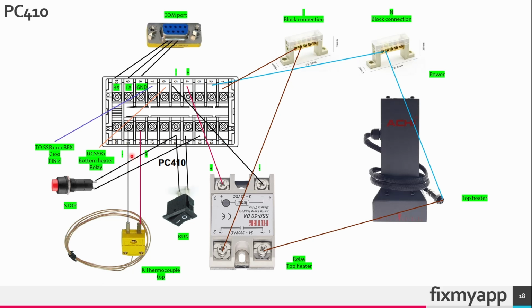The thermocouple to measure the temperature on the top side of the PCB board will be connected here on terminals 18 and 19. 18 is the positive side and 19 is the negative side. The run switch will be connected to terminal 14 and 15. And the stop push button will be connected to terminal 15 and 13.